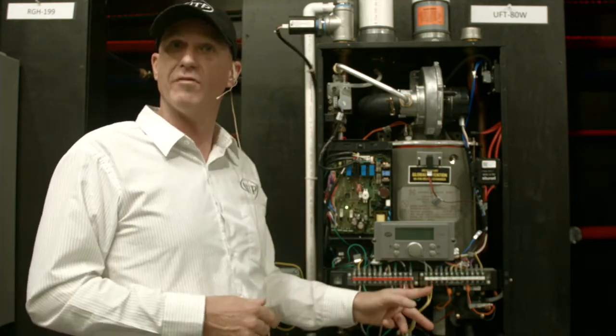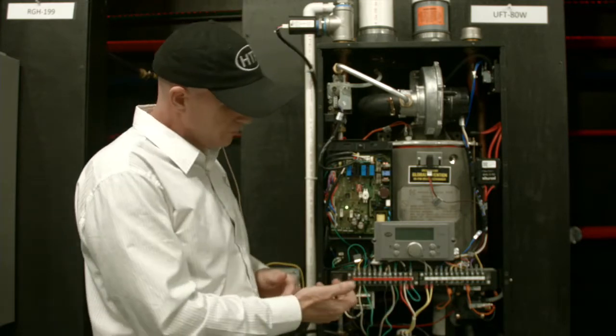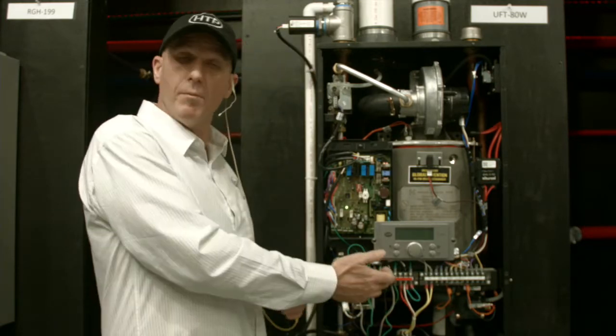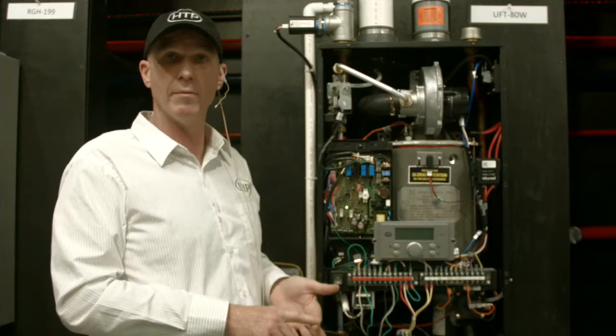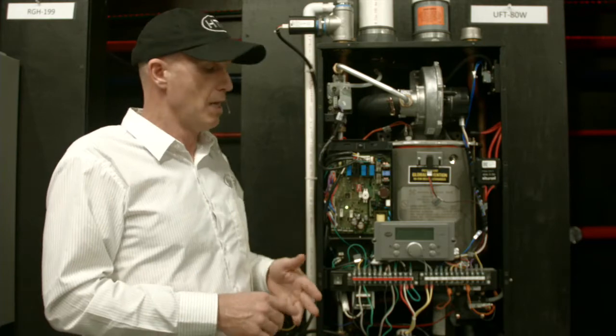And then it has the low water cutoff, which is the switch side of the safety. As you move over to the line voltage side, we have our incoming power, three pump outputs. We can control a boiler pump, a system pump, and a domestic hot water pump.